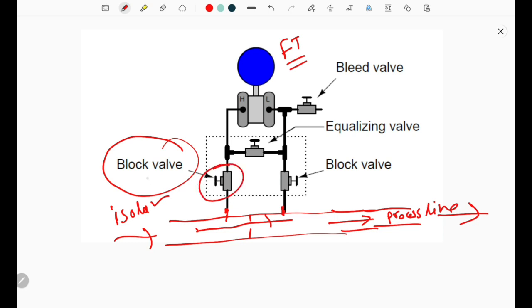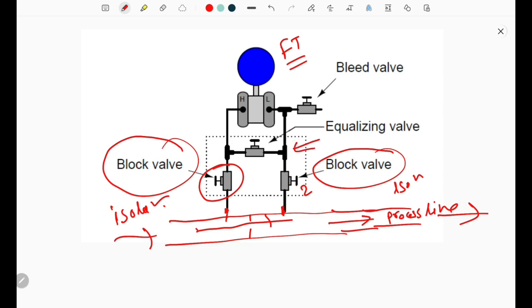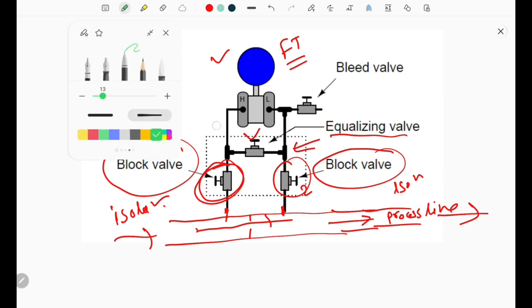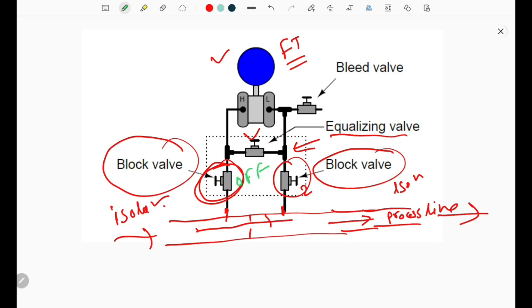This is the first valve, called the block valve or isolation valve. This is the second valve, also called the block valve or isolation valve. The third valve inside the three-way manifold is called the equalizing valve. Whenever we want to check the zero of the transmitter, we close both block valves and open this equalizing valve. When we open this valve, each tapping or each side of the transmitter will have equal pressure.